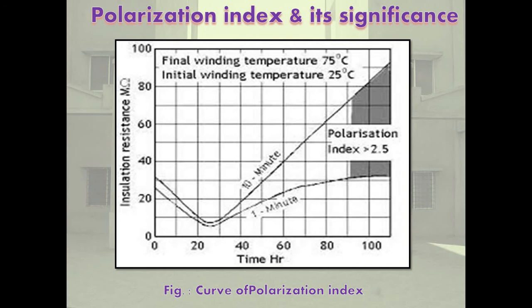For large and HV transformers, 10 minute and 1 minute meter readings are taken instead of the IR 60 and IR 15. Polarization index now gives the true idea about the quality of insulation.